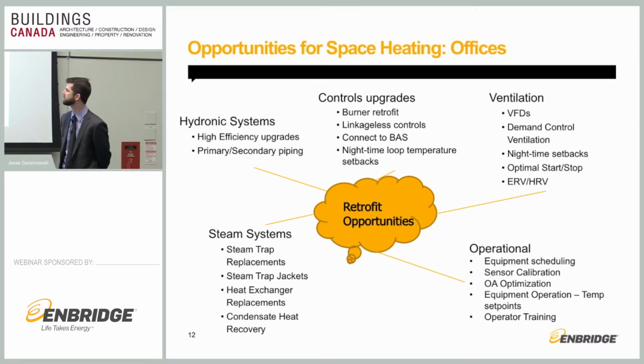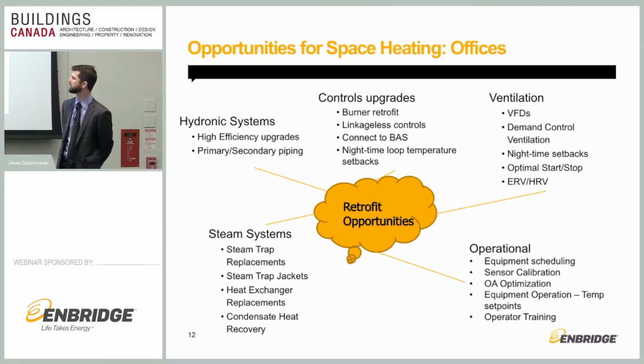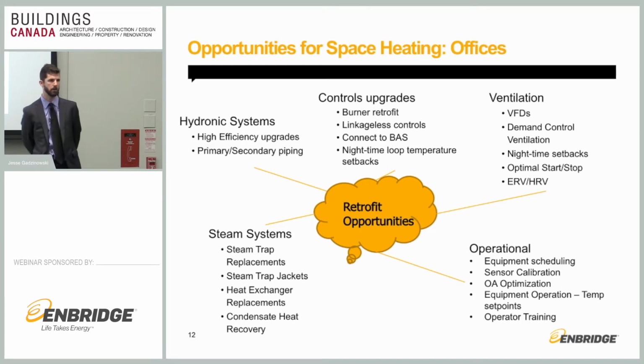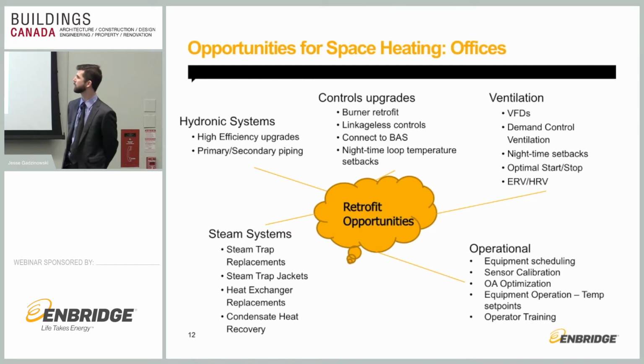For steam systems, we're seeing a lot of steam trap replacements and steam trap jackets. Essentially just limiting those leaks. Depending on how many steam traps you have in a facility, there can be a substantial amount of leaking steam, which is actually a very large loss. And you can have easily 100,000 cubic meters coming out of a large building just in steam leaks if you haven't really maintained that system appropriately.